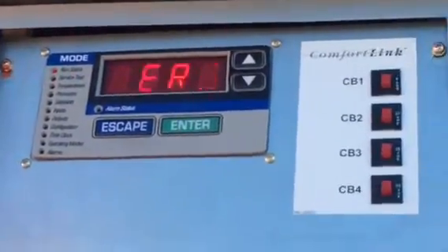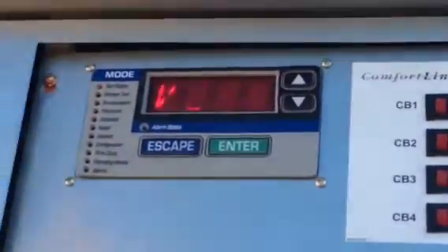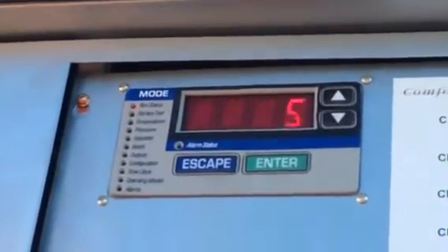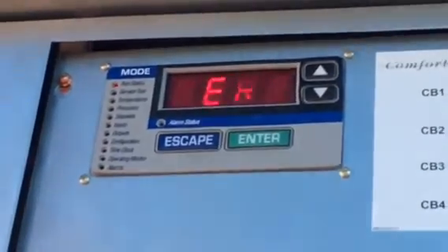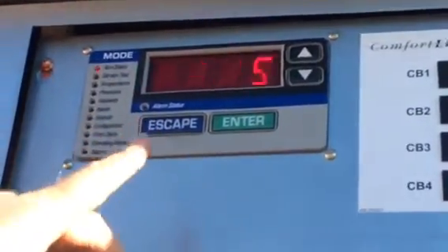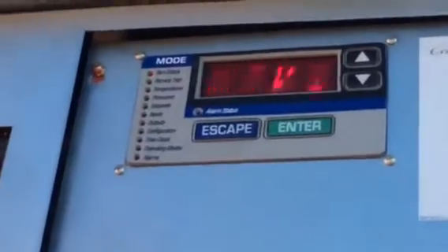We missed looking for the other thing through run status. Sometimes if troubleshooting things come up, or if you call my guys in tech support, they know more than I do, thank God, right? Sometimes I'm going to ask for software versions. Within run status, if I scroll all the way down to version, it gives me a choice of main baseboard, ECB1, ECB2, the marquee itself, navigator. If I was plugged in, it would give me that information.